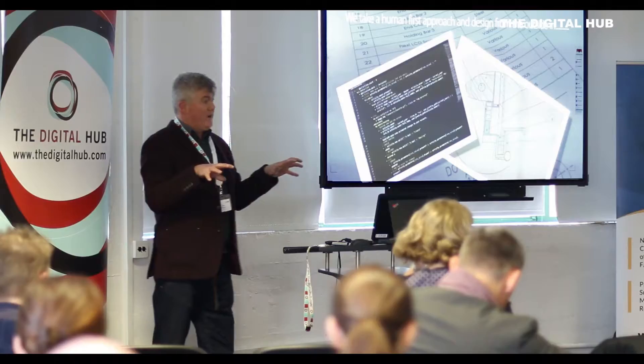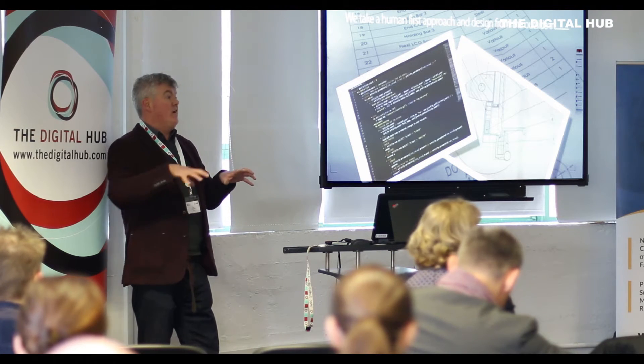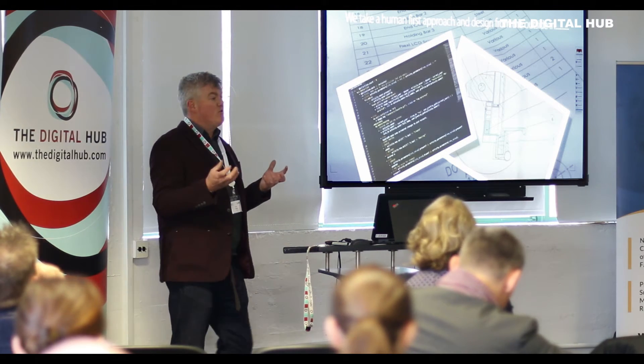What's really important is using human factors and device design early in the process — designing from the outside in, so rather than being technology driven you're driven by the human being on the outside. But the most important thing is that the FDA and the regulatory authorities tell us that we have to do this now. They're telling us formative testing with users early in the process is a crucial part of your design process.